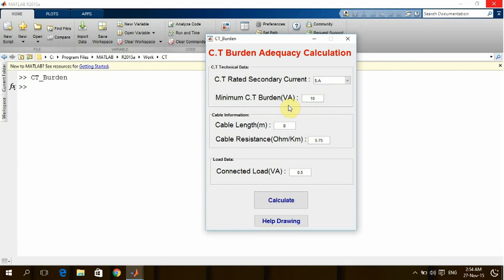Now the question: why is the burden of the CT very low in the volt ampere? In fact, the CT in ideal condition must be connected to a short circuit, meaning that the voltage on the secondary terminals of the CT is zero.